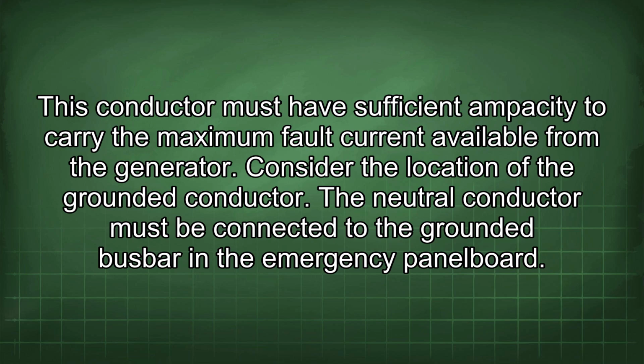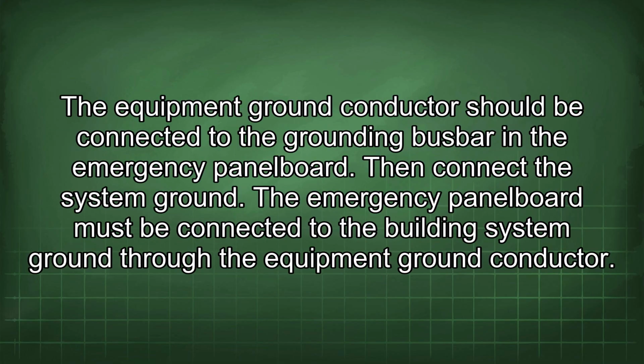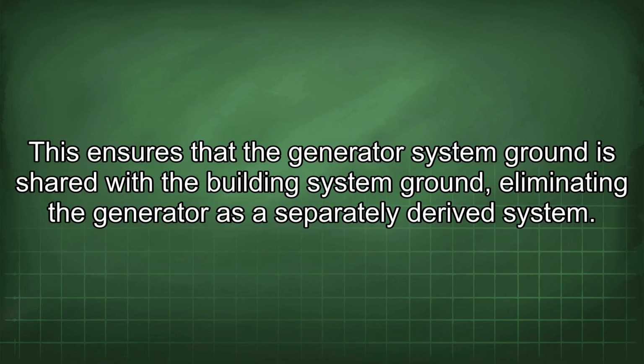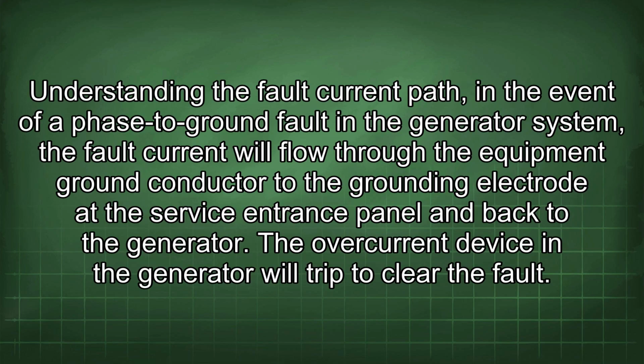Consider the location of the grounded conductor. The neutral conductor must be connected to the grounded busbar in the emergency panel board. The equipment ground conductor should be connected to the grounding busbar in the emergency panel board. Then connect the system ground. The emergency panel board must be connected to the building system ground through the equipment ground conductor. This ensures that the generator system ground is shared with the building system ground, eliminating the generator as a separately derived system.